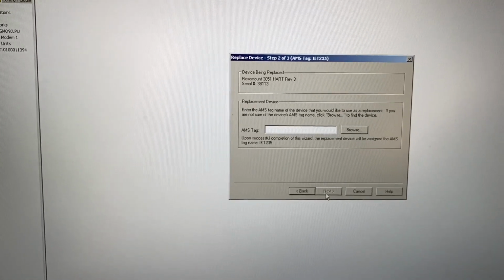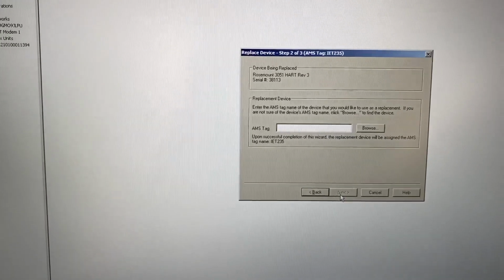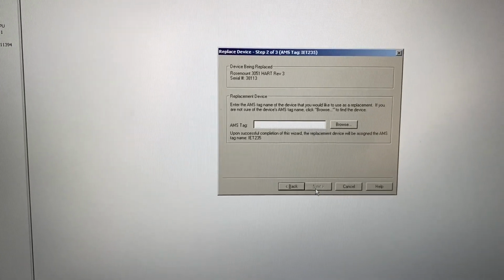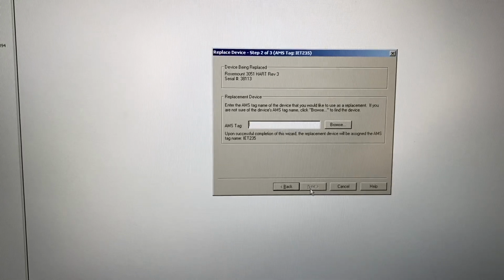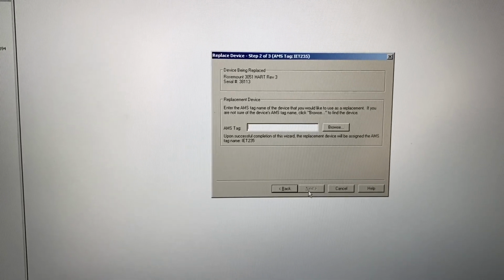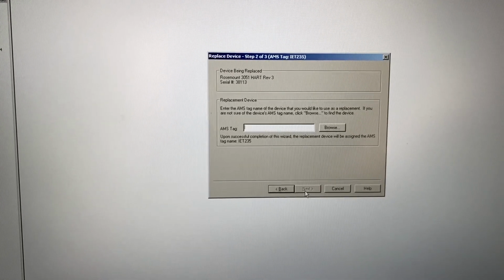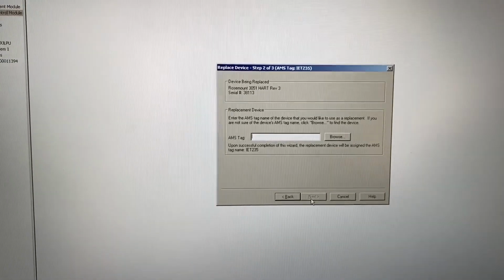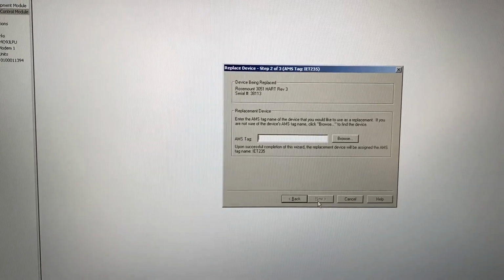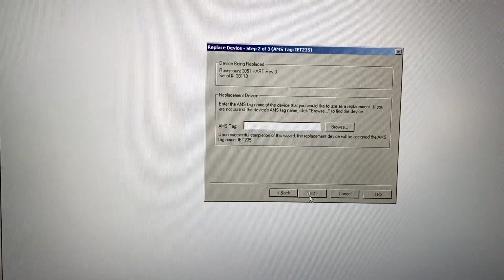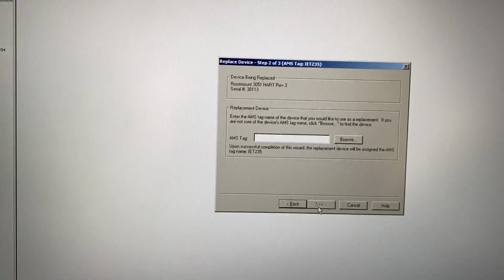Click next, and it asks to enter the AMS tag name of the device you'd like to use as the replacement. If you're not sure, we'll need to make some changes — wiring up our HART modem to the new device, since right now the replacement device isn't on our system. Let's go ahead and do that.